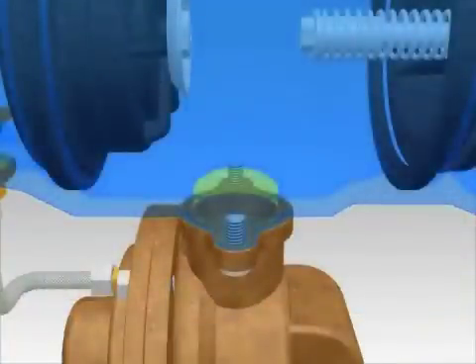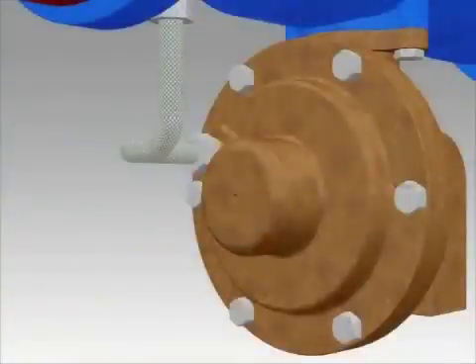Place a rag in the body opening to prevent any objects from falling into the relief valve. Before servicing the relief valve, make sure to check the troubleshooting section of the instructions. The most common cause of discharge from the relief valve is debris in the number 1 check valve.